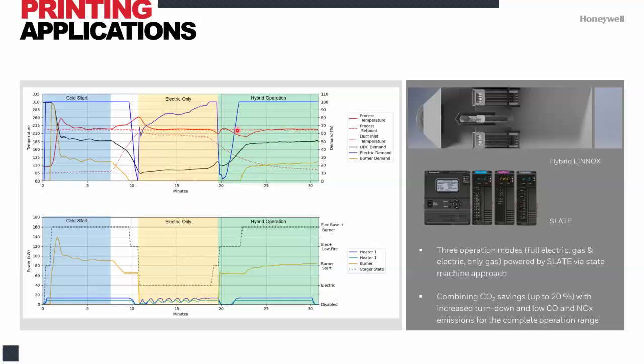We stabilize after a short period, and now we're in a hybrid operation where burner and heaters are enabled together. In our newest runs, we've been able to smoothen out these transition pieces almost perfectly. With this, we estimate a significant turn-down with stable CO and NOx emissions, as well as up to 20% CO2 savings if the electricity is carbon neutral.